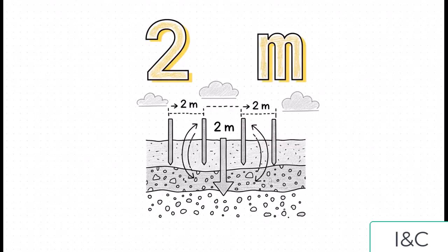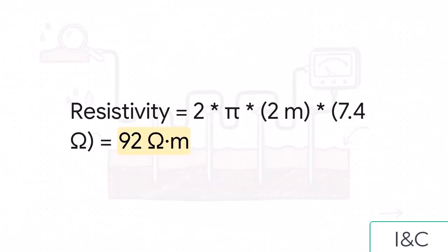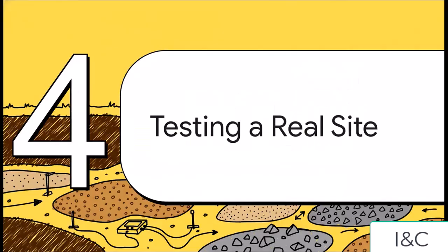We got out our tape measure and spaced our rods exactly 2 meters apart, so our A value is 2 meters, which also means we're measuring the soil's resistivity at a depth of about 2 meters. Now we plug those numbers into our formula: 2 times pi times our 2-meter spacing times our 7.4 ohm resistance. Run that through a calculator and you get a soil resistivity of about 92 ohm meters at that specific depth. Done.